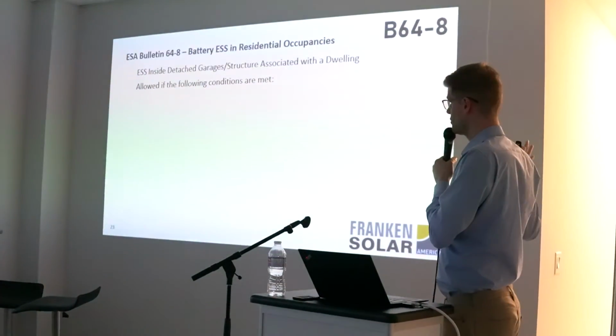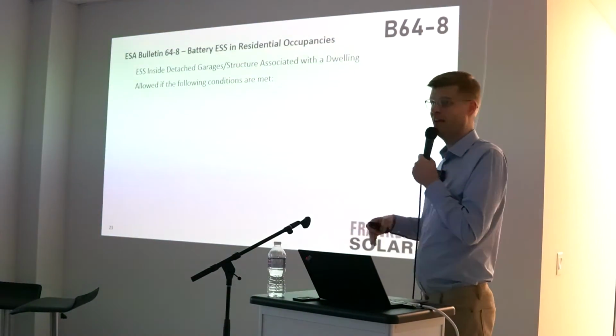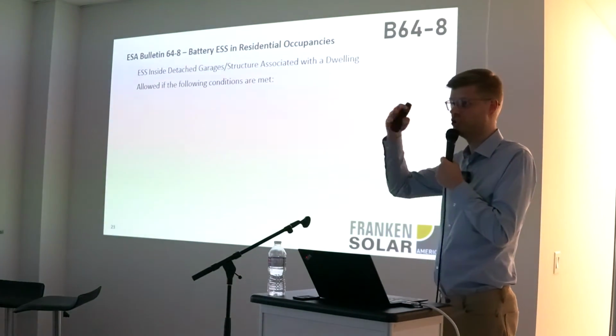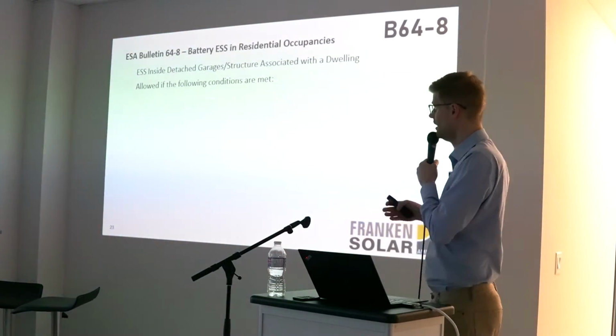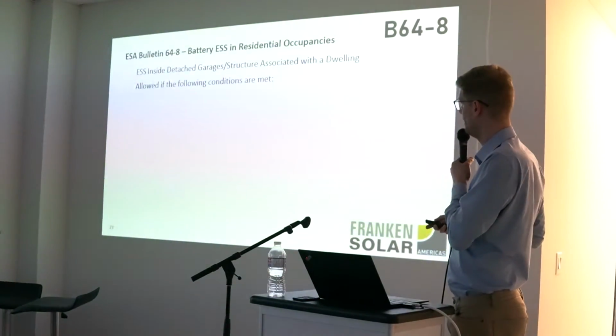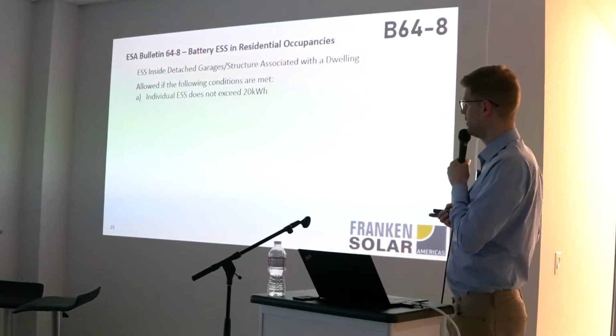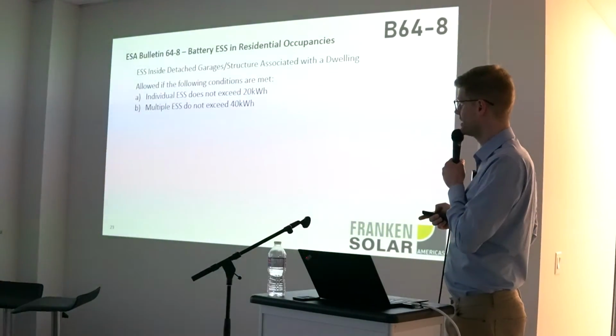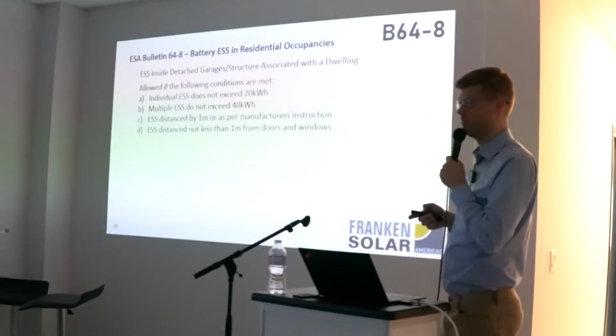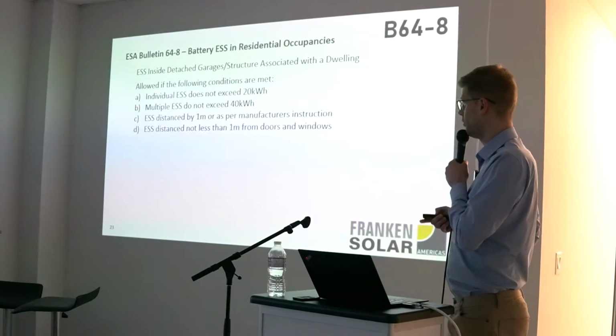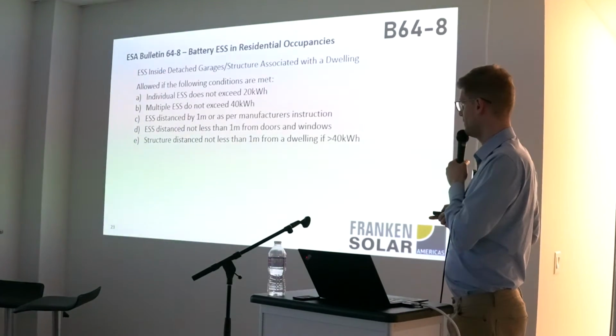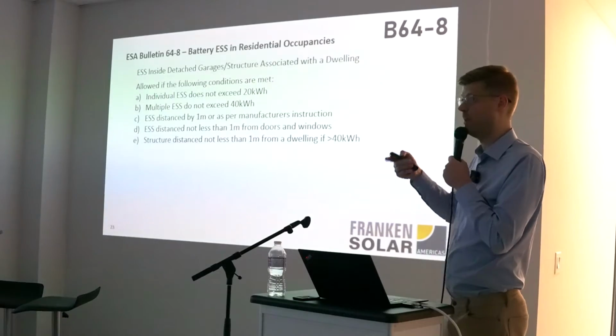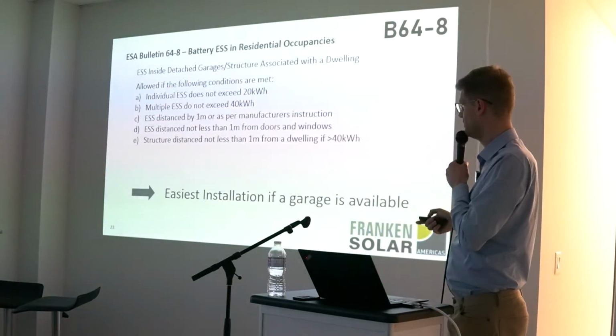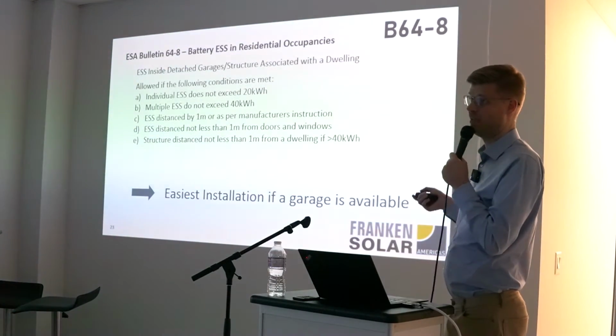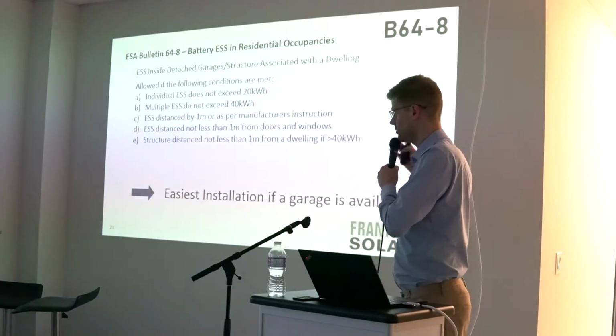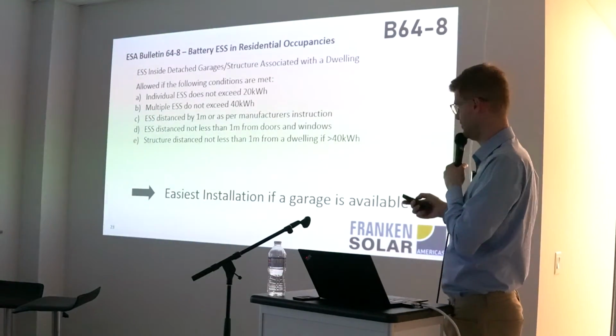If you have an entirely detached structure, like a dedicated dwelling, let's say you have a farm, and the farm has a house, and you have probably a garage or a shed or an extra electrical room where you have your pole and your transformer on it, or whatever structure that is on the same property together with a dwelling. Then you can still do the same thing as we had, 20 kilowatt hours for a single system. You can do 40 kilowatt hours for that system total. You still have to have the spacing, and you still have to have the distance, because it's now in a building, at least 1 meter from doors or windows for egress path. And the structure, so the building, needs to be at least 1 meter apart from your actual dwelling if you want to be in that category. And the easiest installation, again, is if you have such a house, garage, whatever barn available to you that is separated from the residential dwelling.